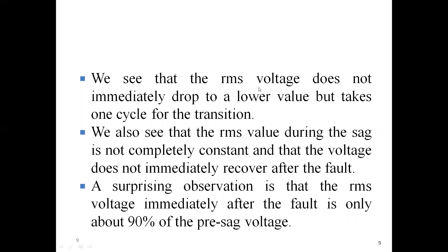To summarize what we have seen from the figure: the RMS voltage does not immediately drop to the lower voltage level but takes one cycle for the transition. We also see that the RMS voltage during the sag is not completely constant, and that the voltage does not immediately recover after the fault. The other surprising observation is that the voltage after restoration is only 90% of the pre-sag voltage.